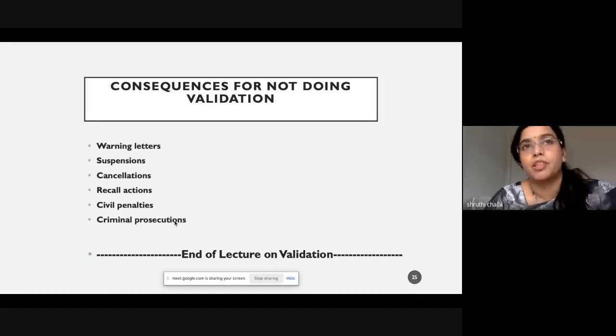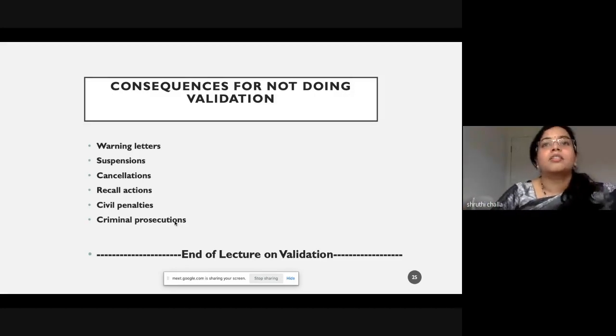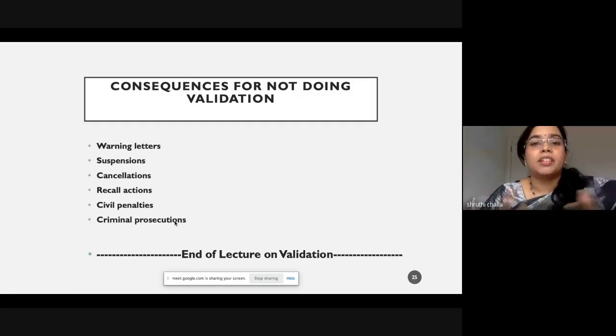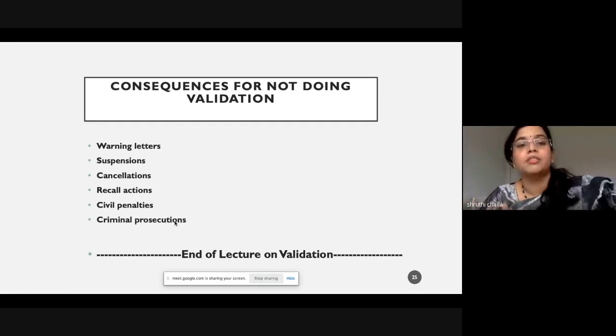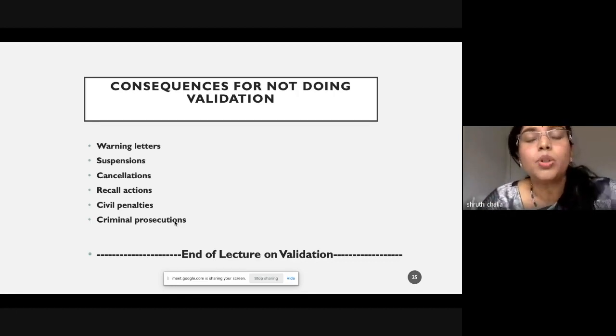But if we validate the process beforehand, every time we do lots and lots of batches, we would have a high level of confidence that we would pass the quality control test. So that is the idea of validation. That's applicable obviously to process as well as equipment. If we have good equipment and it's properly installed, it operates correctly and it performs as intended, we don't have any issues, we can keep on running it. If equipment breaks down in a big manufacturing facility, the production would be interrupted. That would be very expensive. So that's why we need to place that equipment on a preventive maintenance schedule, and routinely maintain it before it breaks down. Those are the concepts of validation.